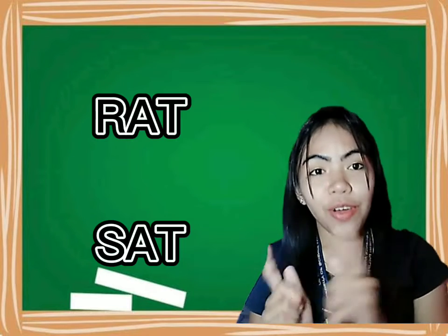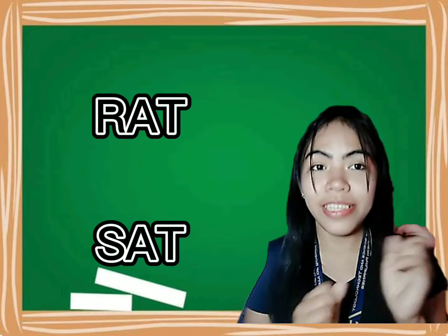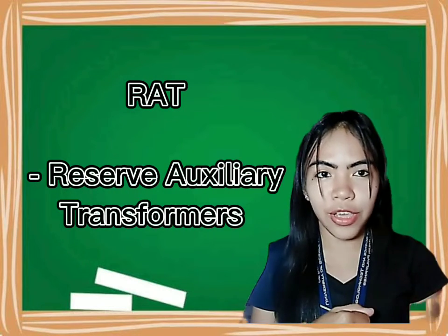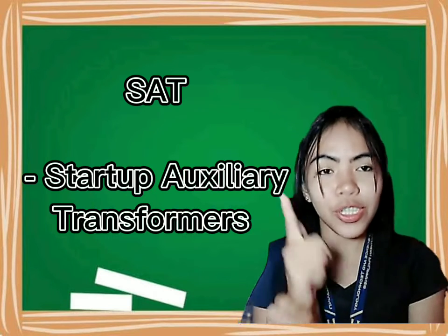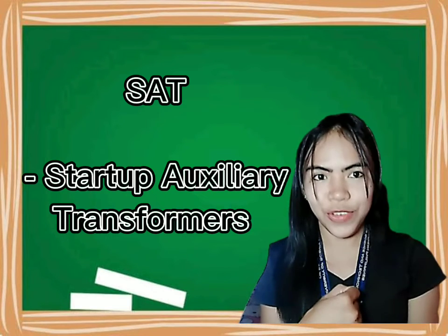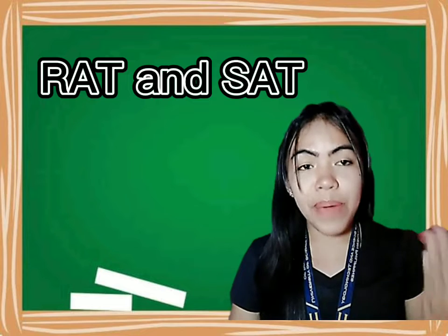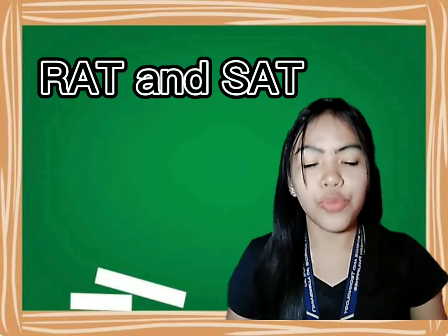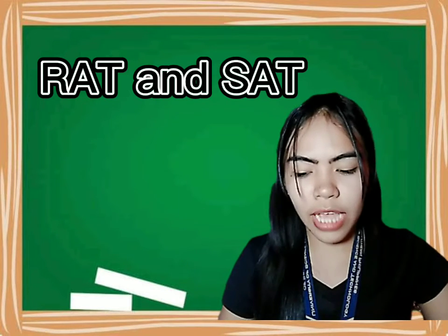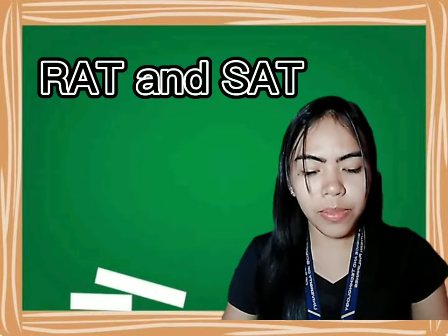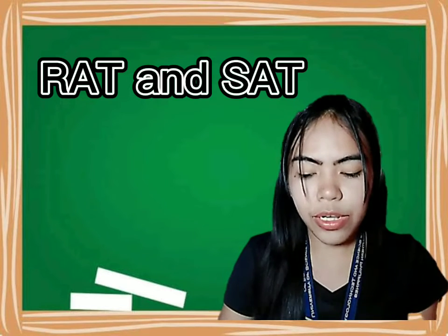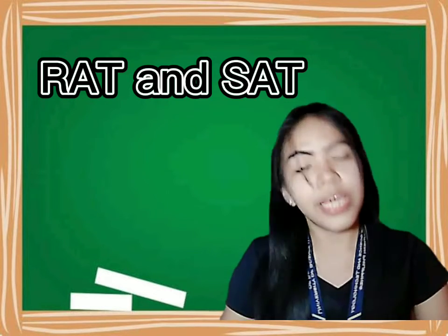We also have the RAT and the SAT. The RAT is the Reserve Auxiliary Transformer, and the SAT is the Startup Auxiliary Transformer. They are both backup transformers, which are connected to an off-site high-voltage system supplying the plant auxiliary power during startup or outage periods. So those are the types of transformers.